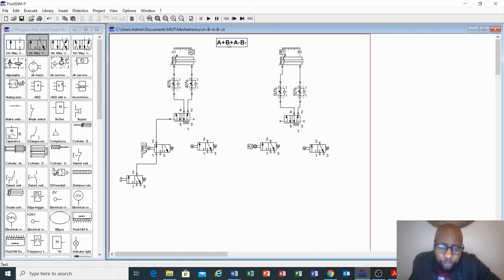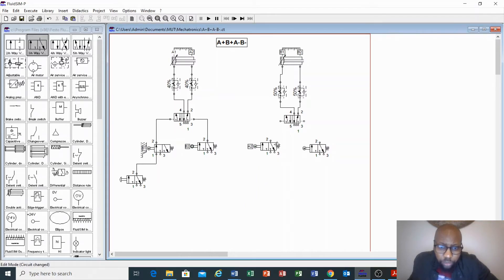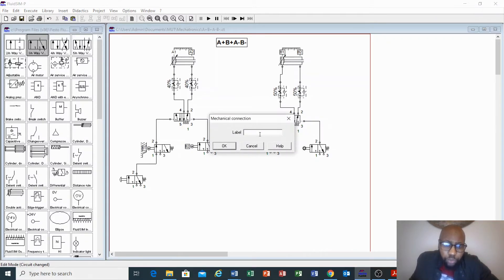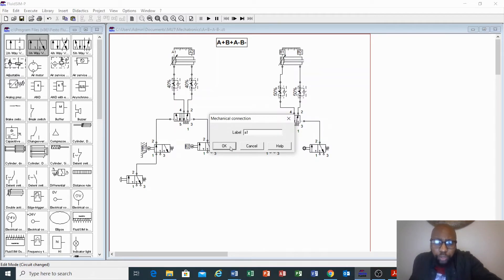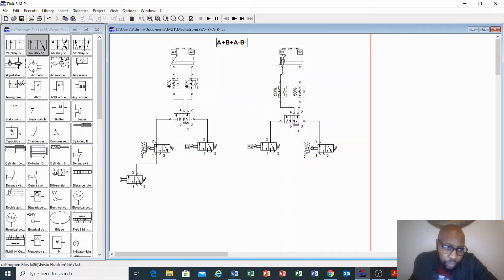If A2 is true, cylinder B will extend. Now we are going back — this is to reverse cylinder A. For cylinder A to reverse, we need B2 to be true. Then this will reverse. If we want to reverse cylinder B, A1 should be true because cylinder A will be fully retracted, then A1 should be true to make the B-cylinder retract.